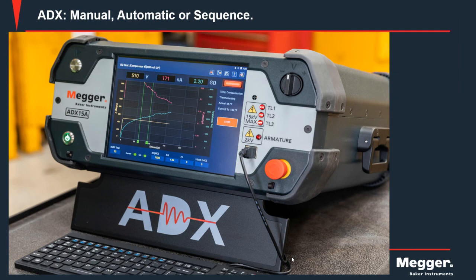Now, what that means is if we hook it up to a motor that we want to test, we can run all of those tests in a sequence by just standing back and watching it, which allows the unit to be very fast through the test sequences, and also to be able to record all that information in one nice report. Now, that report gives us pretty much all of the information that we would need to make a diagnosis of whether the motor needs any attention or not.